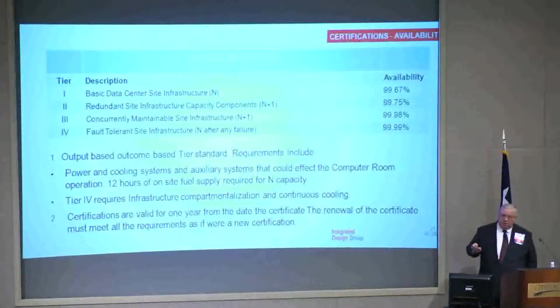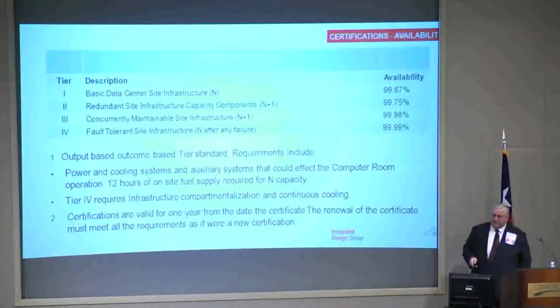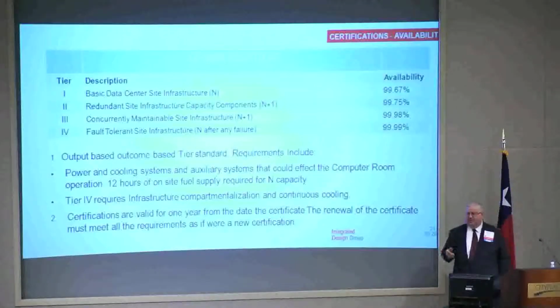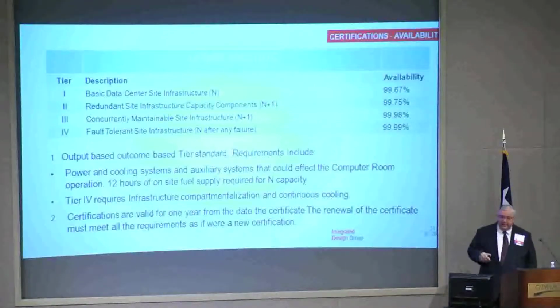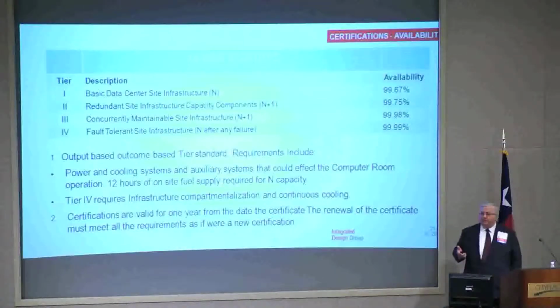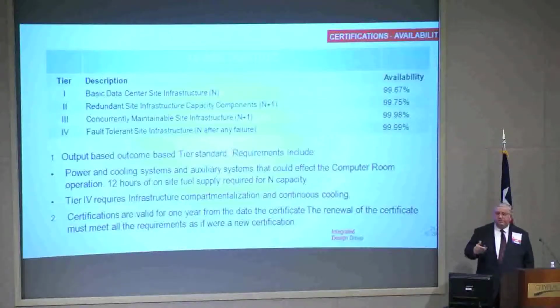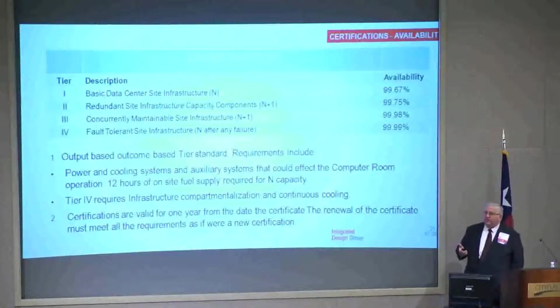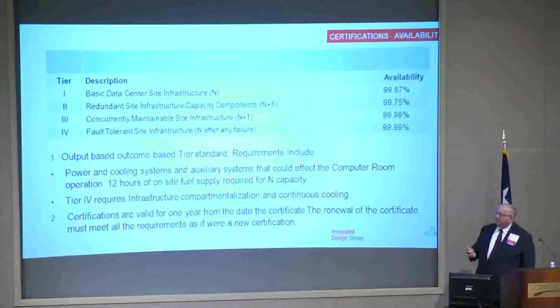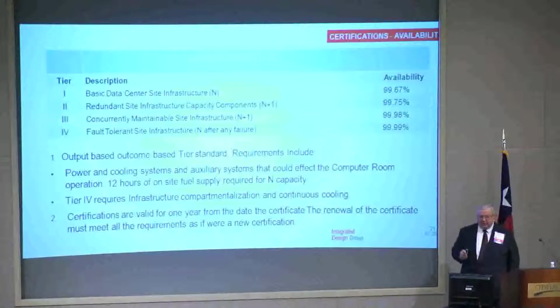Their tiers are 1 through 4, with various levels of availability, up to tier 4, which is 99.99%. They only have a few basic requirements. One is 12 hours of fuel, and that doesn't matter if you're tier 3 or tier 4. That's all they require. Generally clients want more than that, but that's all that's required in their specification.